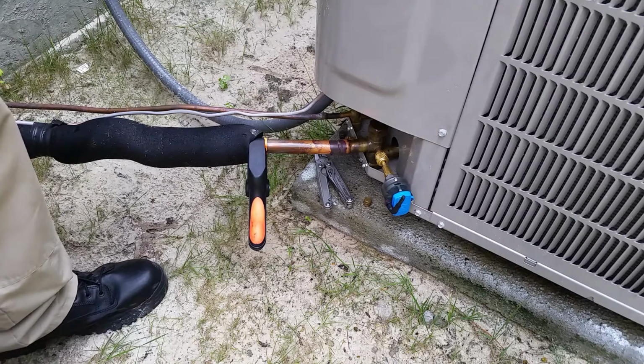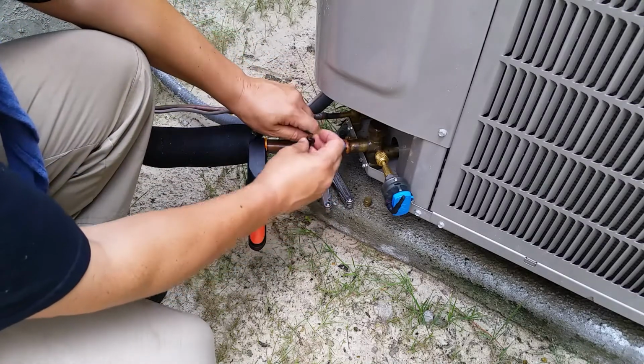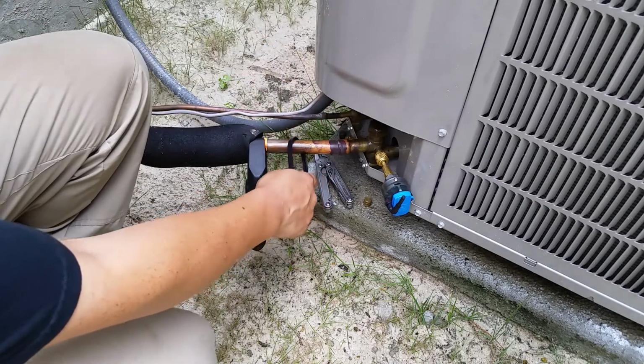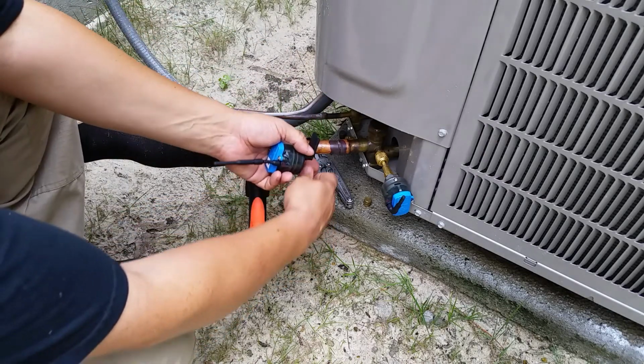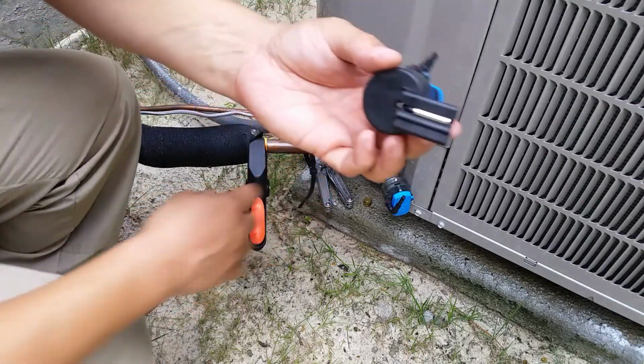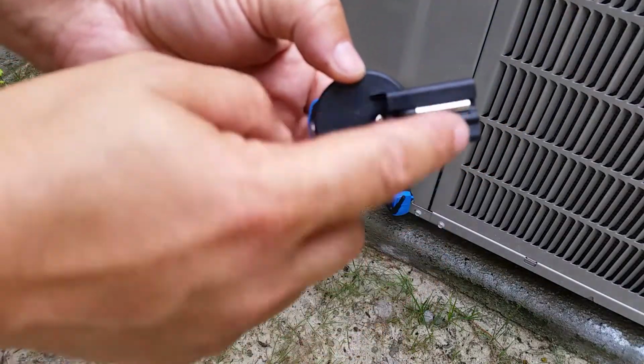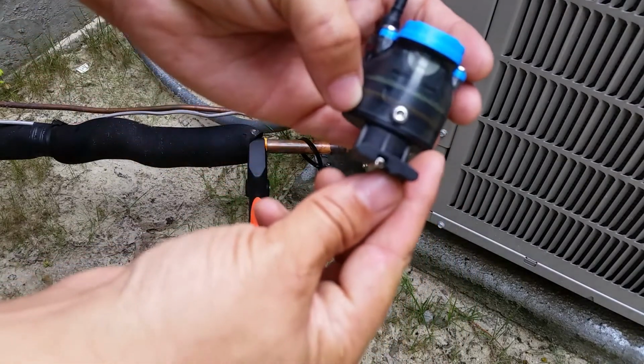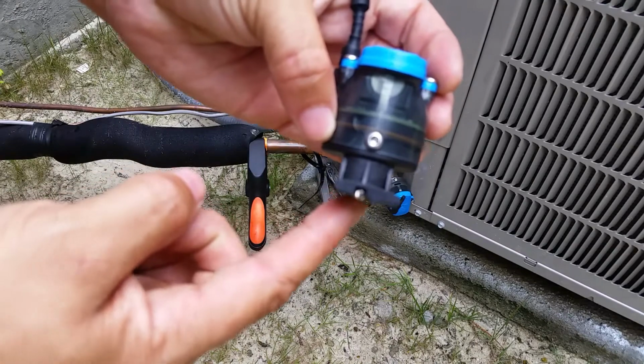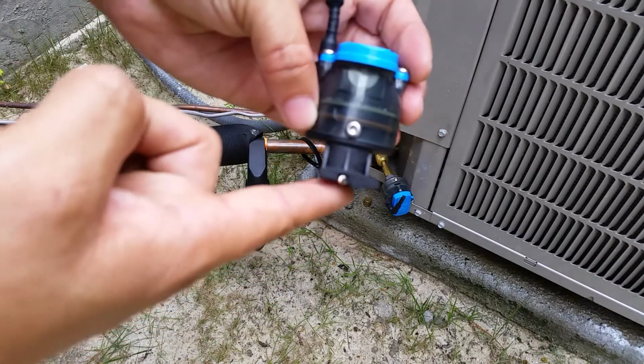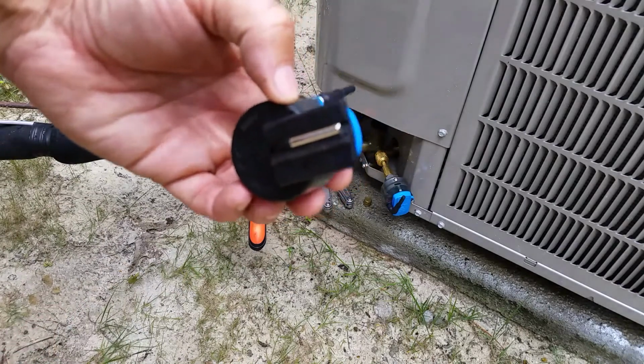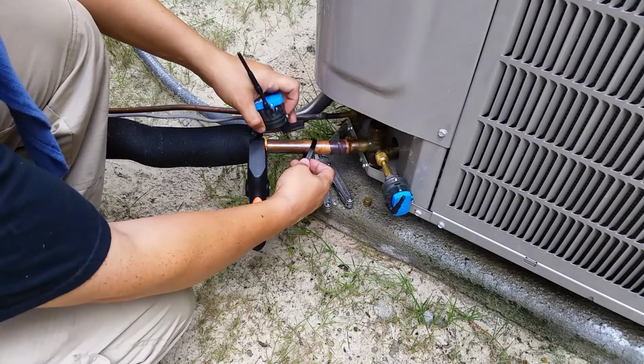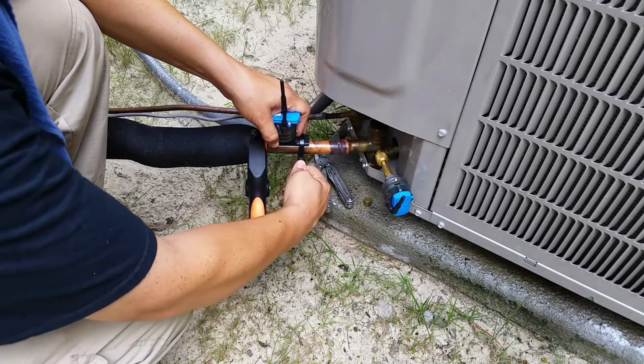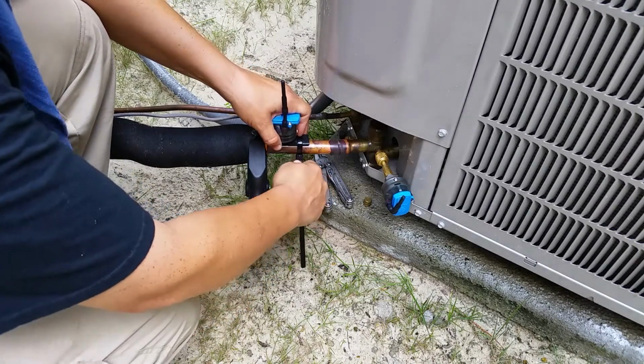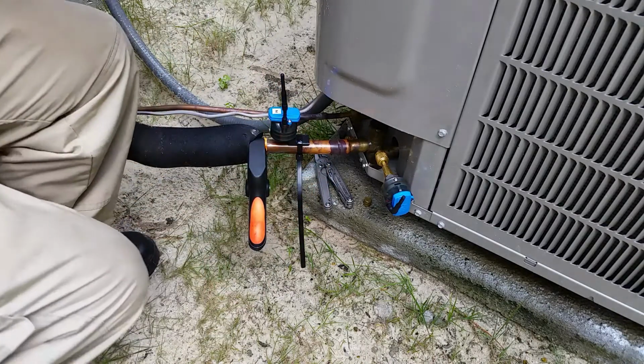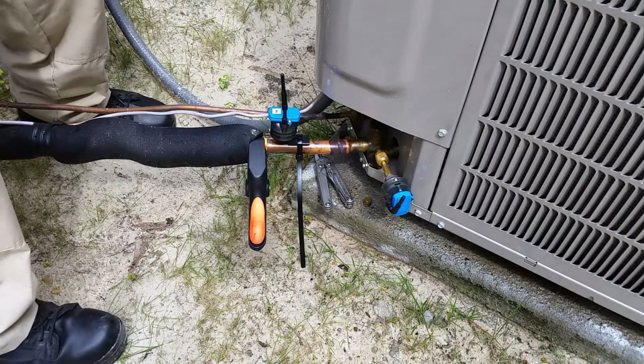Go ahead and put the suction on first. Just secure the zip tie on there. And one other thing on here, you can see you have a little ridge here. It's just for different dimension pipes. You just want to make sure that your pipe is coming in good contact with the temperature sensor on there, so you're getting accurate readings. Snug that on there. And we'll do the same thing to the liquid.